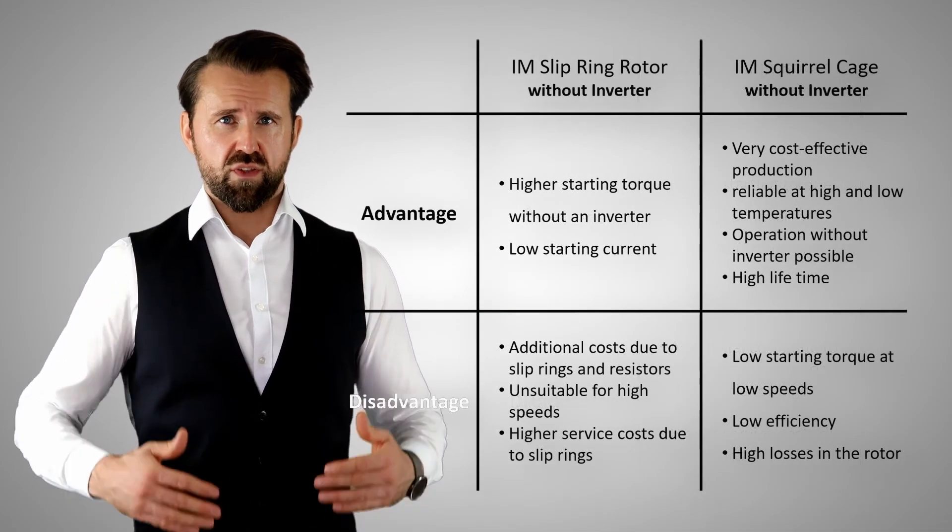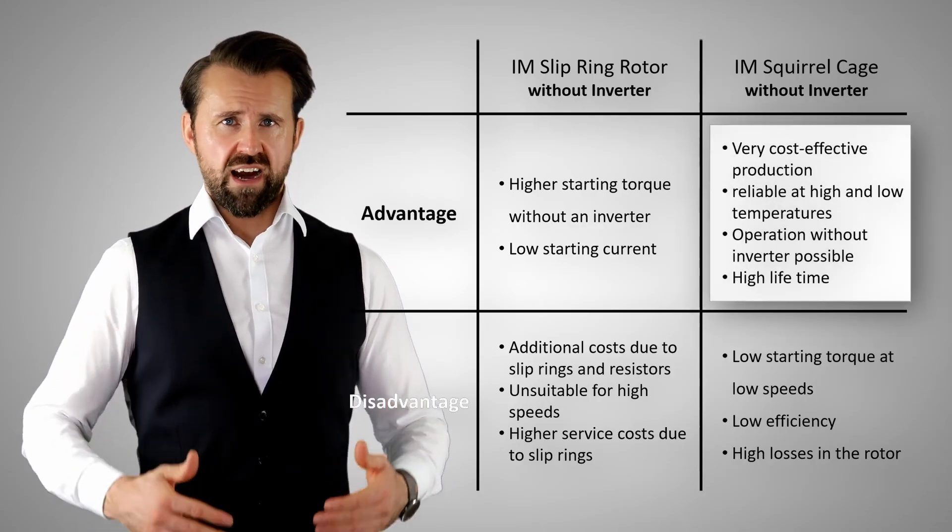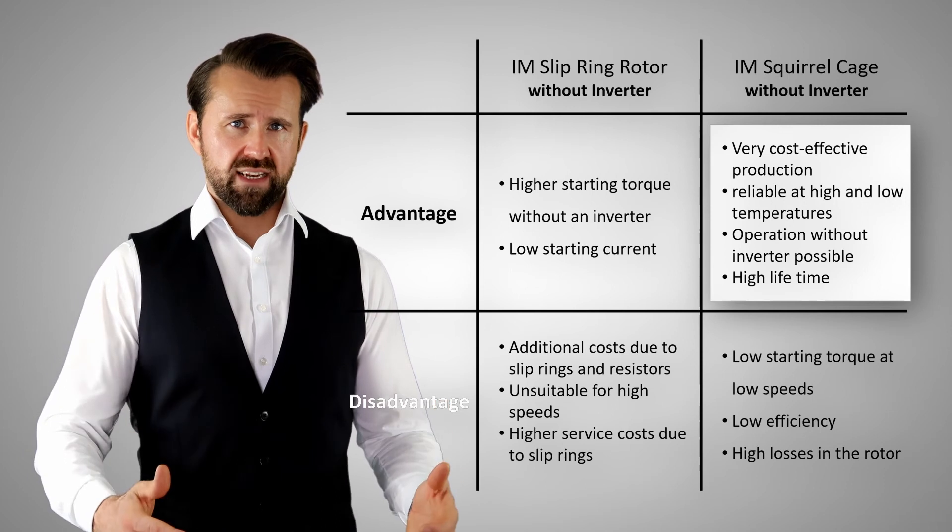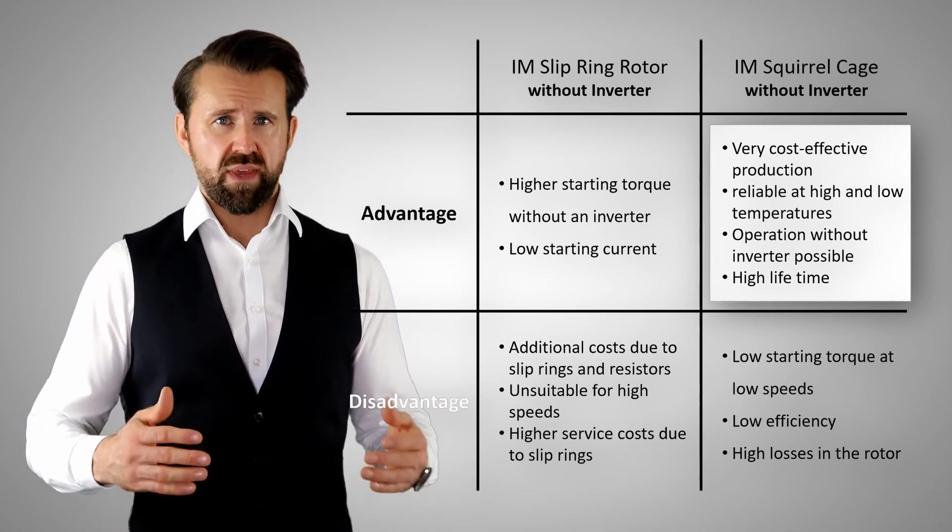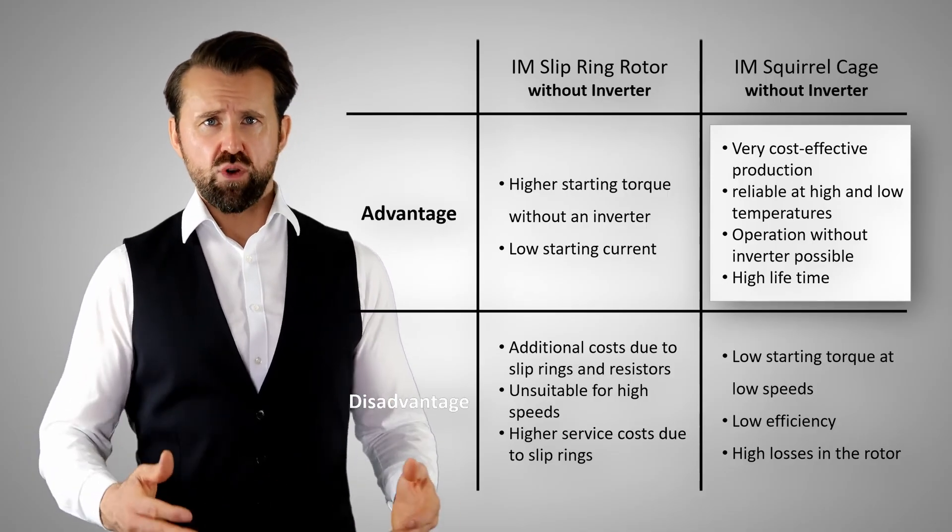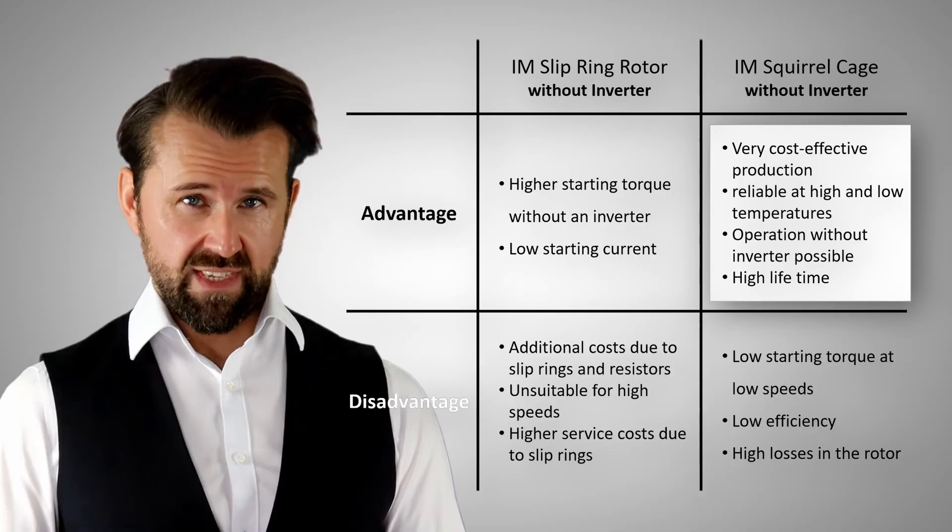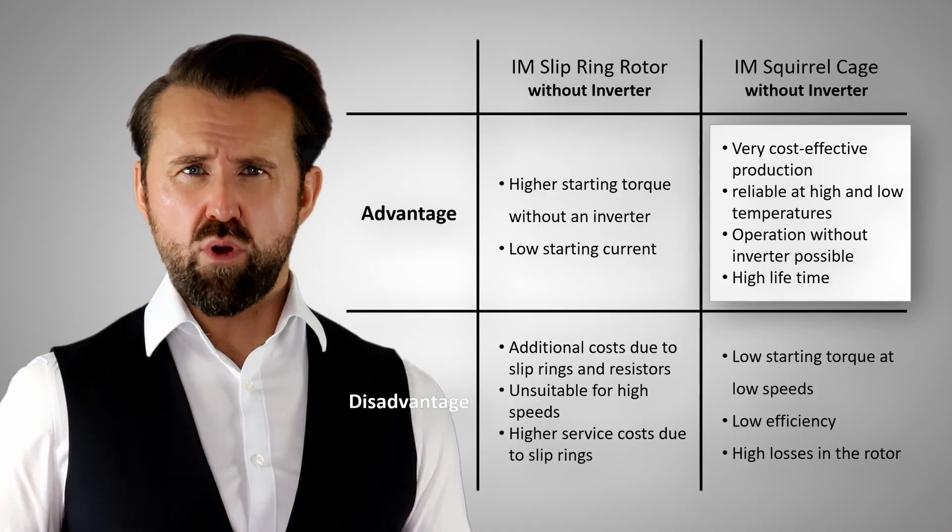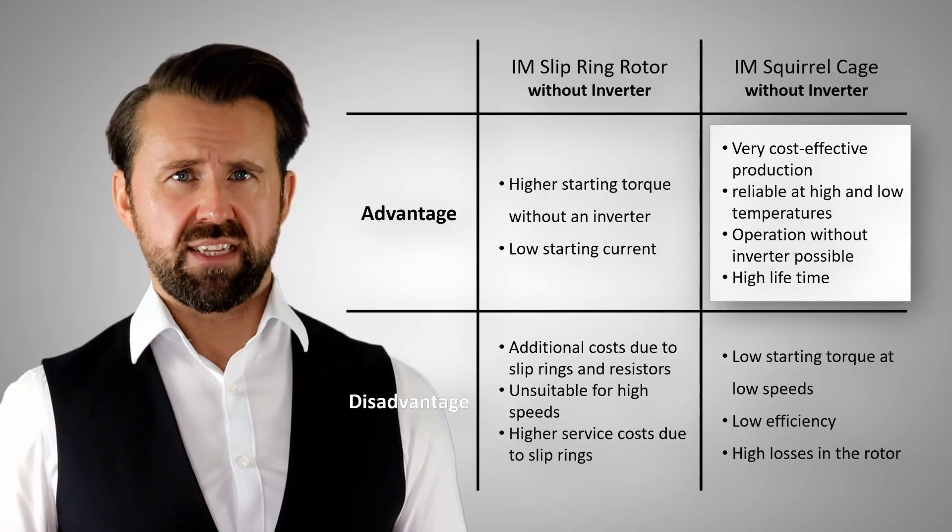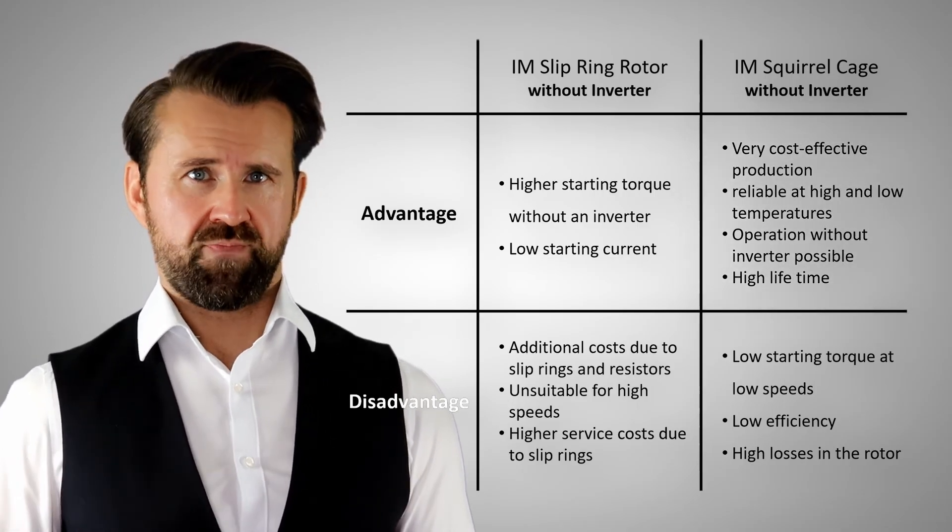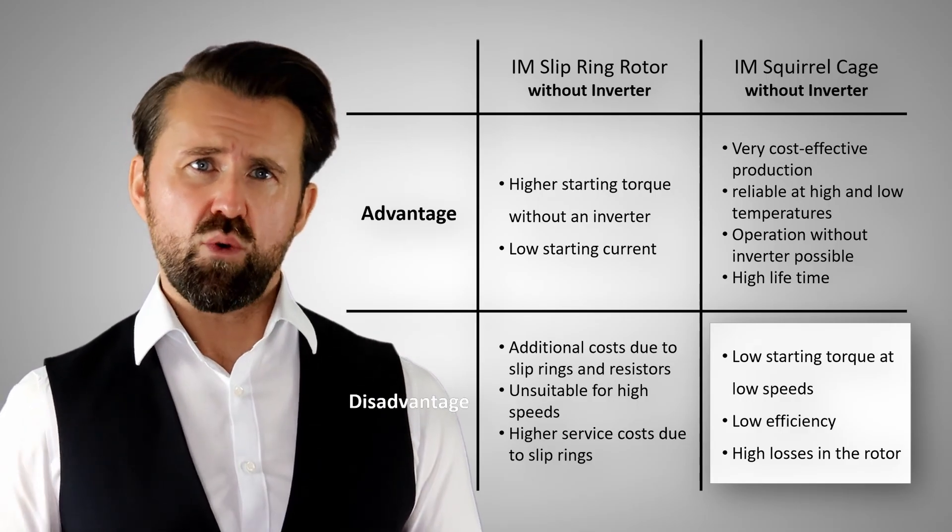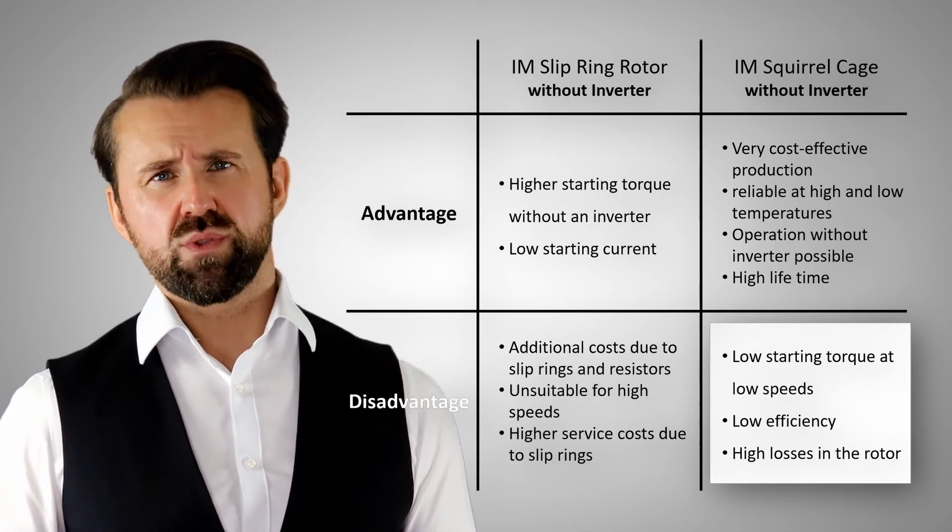The main advantage of squirrel cage induction motors are the low production costs for the rotor compared to a permanent magnet synchronous motor. Only reluctance motors are cheaper. You can find a video about this in the description. The induction motor is very robust against high temperatures. You do not have to worry about demagnetization of magnets like with the PMSM. The main disadvantage is the low starting torque and the low efficiency if you do not use an inverter.